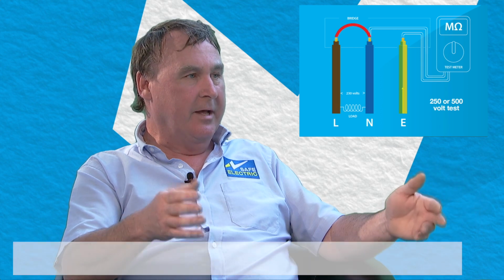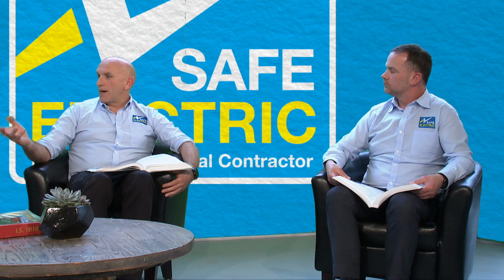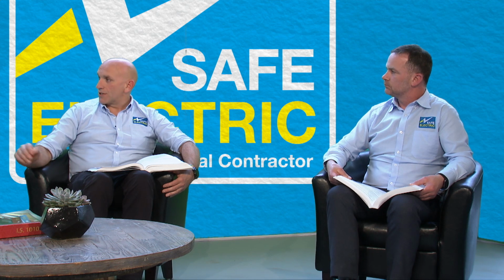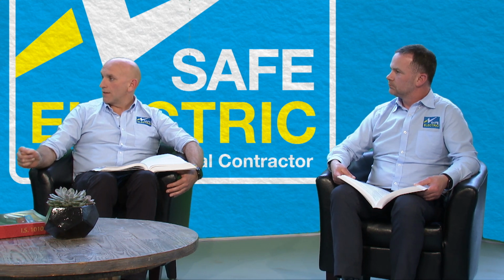Typical values that you would get in Ireland are anywhere between 10 and 100 megaohms. But you will very rarely see greater than 500 megaohms or greater than 999 megaohms. So we'd recommend you do the overall test at the end of the job. It's also a very good method for assessing existing electrical installations as well. I'd agree with that, John, and important.